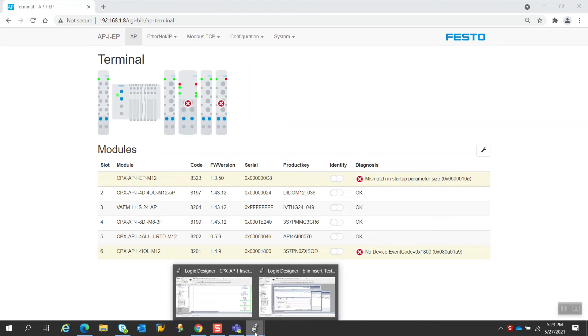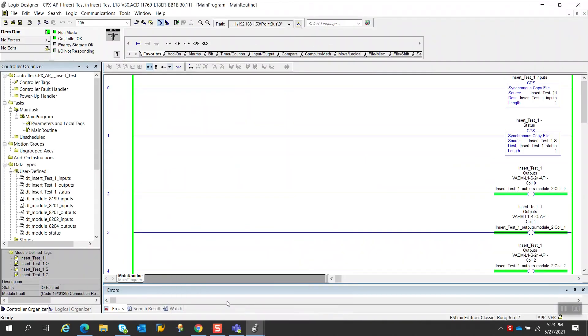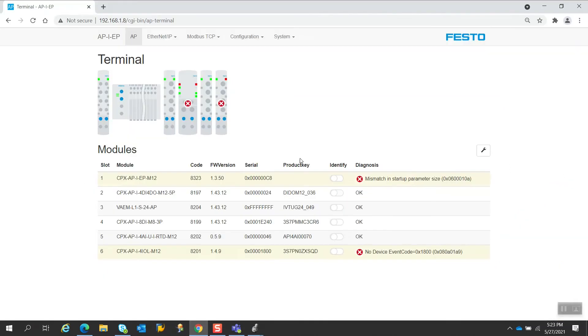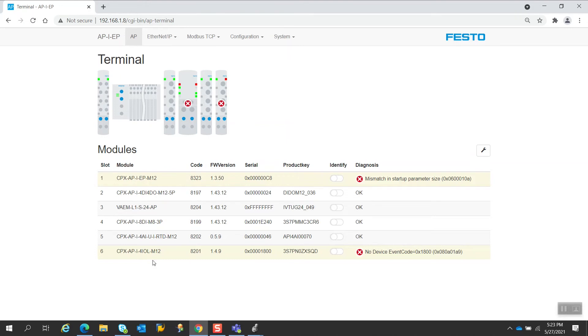If I go to Logix Designer, of course, you're going to see that the system is now faulted because the I.O. size is different. So what we want to do is, now that we have a module inserted before other modules, we want to make sure that the output addresses and the input addresses of all the subsequent modules remain the same, so no one has to go back in and reprogram the addresses of all the modules so their addresses don't get shifted.